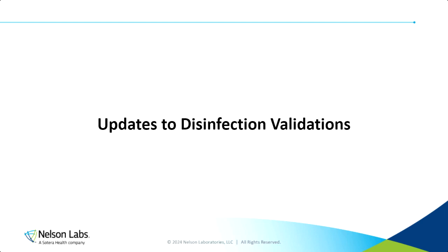Now, just as a quick note, to know if your device needs a disinfection process and whether you need to validate that process, it's going to depend on your device classification. Non-critical devices and semi-critical devices, at minimum, need to go through a disinfection procedure as the terminal step, with high-level disinfection being the minimum requirement for semi-critical devices, and low or intermediate-level disinfection being the requirement for non-critical devices.